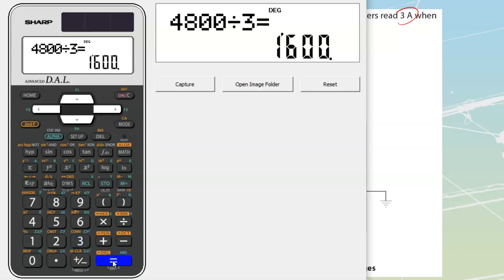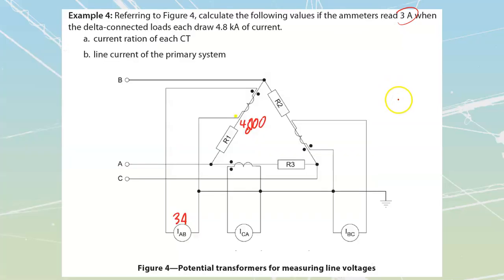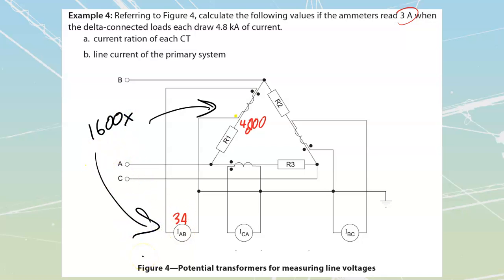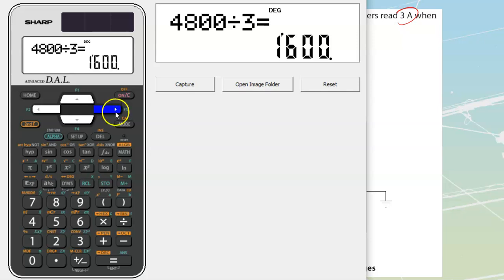Okay, so 4,800 divided by 3 gets me to a value of 1,600. In other words, the current going through the top over here is 1,600 times greater than the current going through my actual CT. Well, what's my CT standard rating? The CT standard rating is going to be 5. So I'm going to take that 1,600 and multiply by 5, and that's going to tell me what I'm going to have.